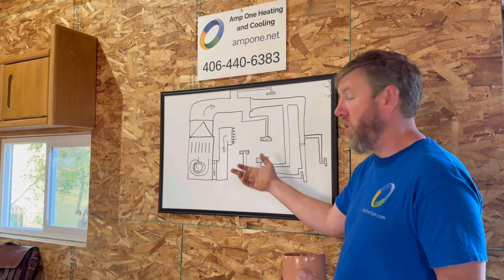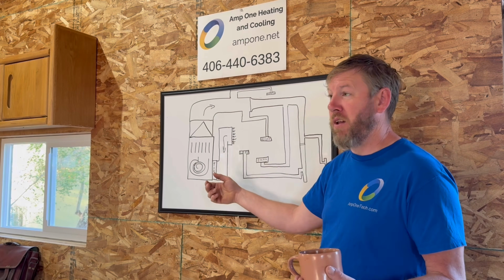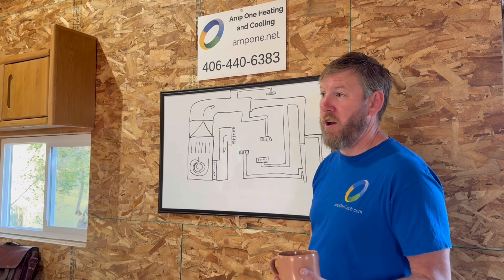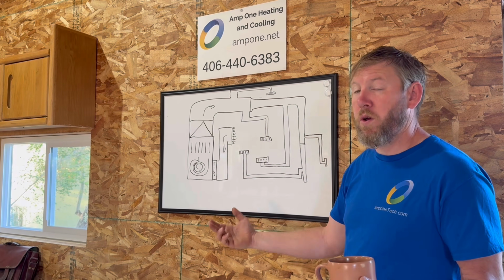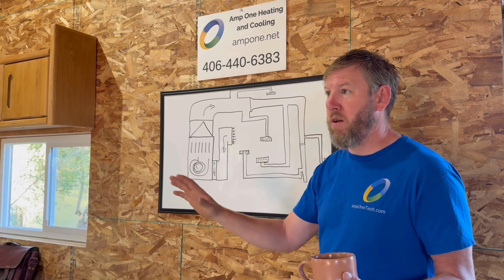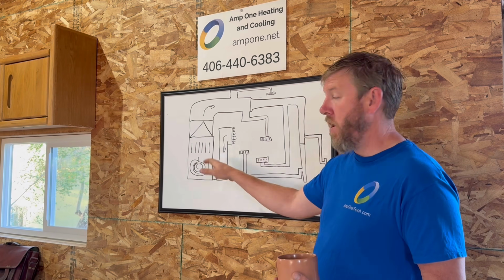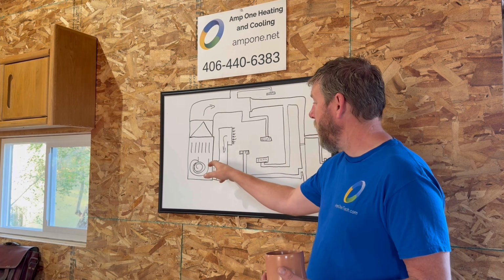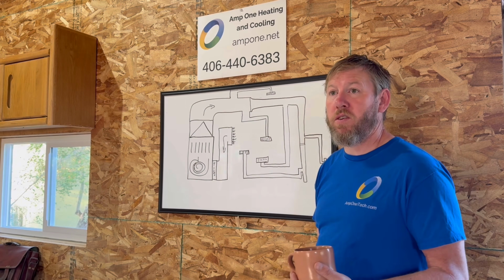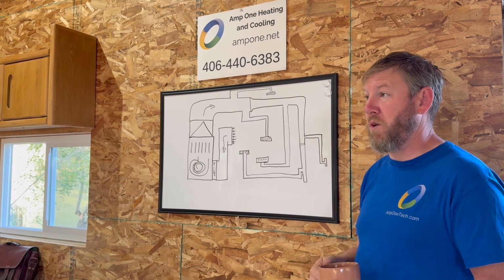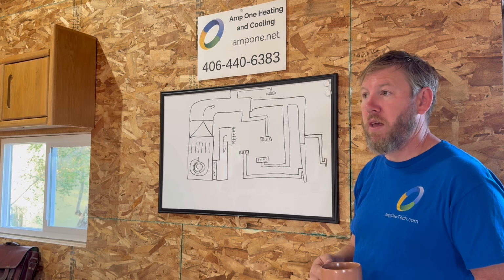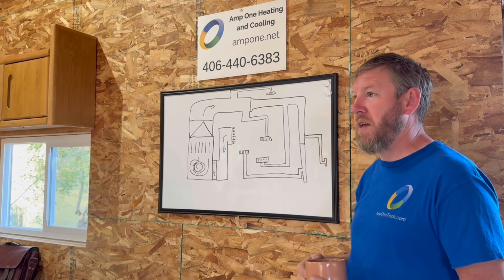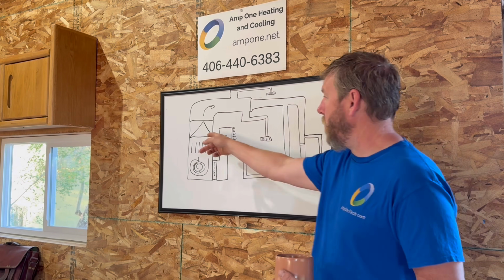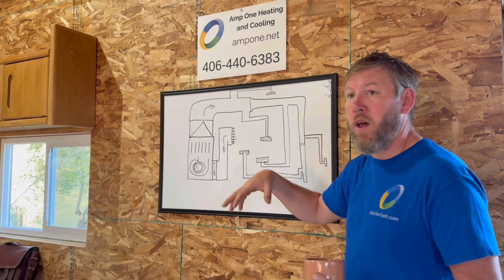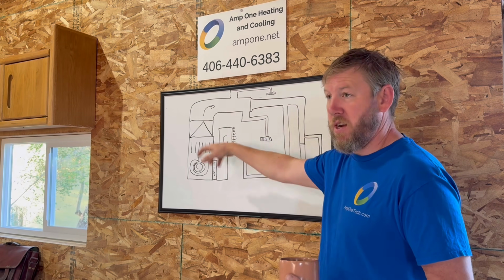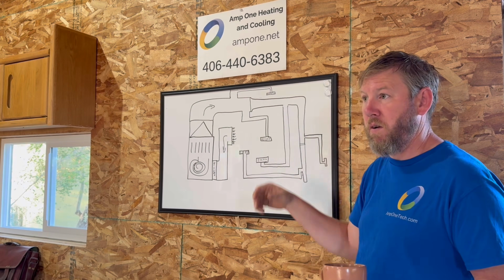Or let's say the ductwork was installed incorrectly and we don't put enough return air back to it. There are some checks we can test with, like static pressure, and those are some other things we're going to get into. But that would definitely cause an airflow issue that would drive the superheat down and cause freeze ups in our coil. So that's why proper duct sizing is very crucial.